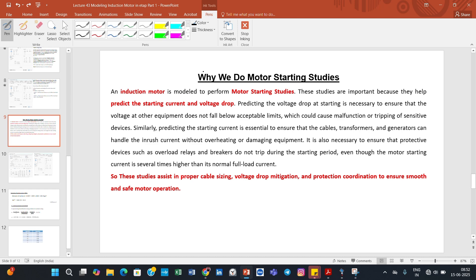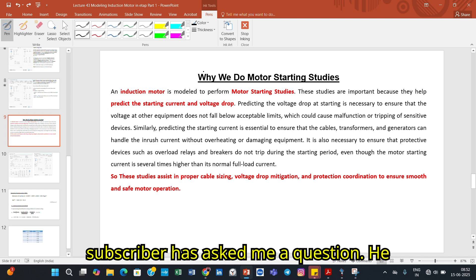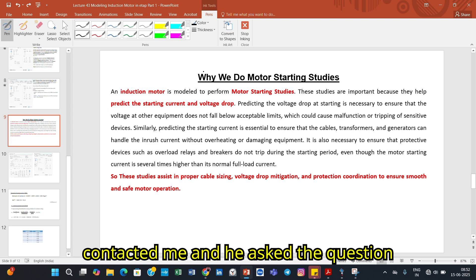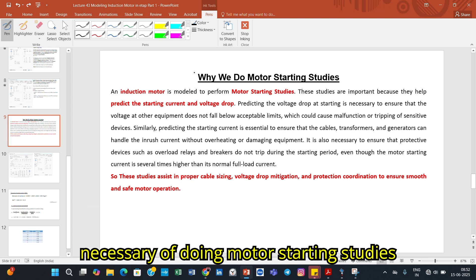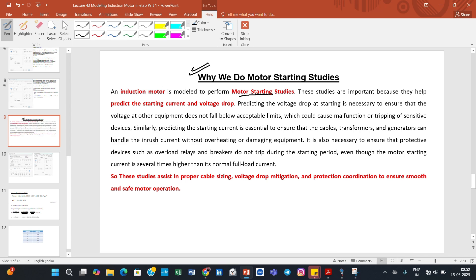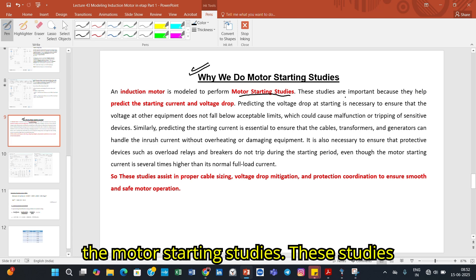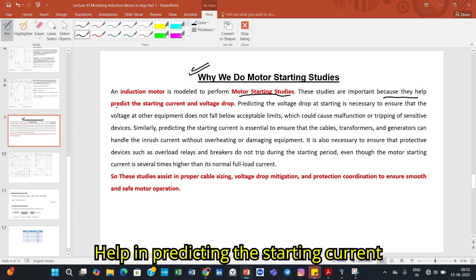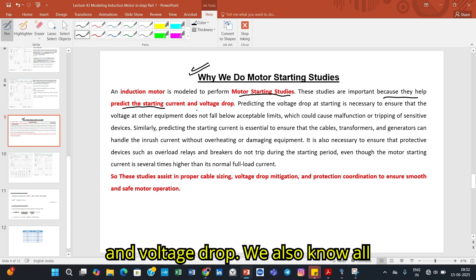Let us start today's lecture. Before starting, one of my subscribers contacted me and asked a question: why do we perform motor starting studies? Why is the induction motor modeled to perform motor starting studies? These studies are important because they help in predicting the starting current and voltage drop.